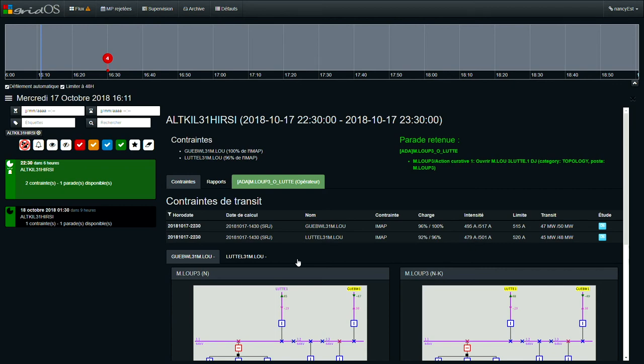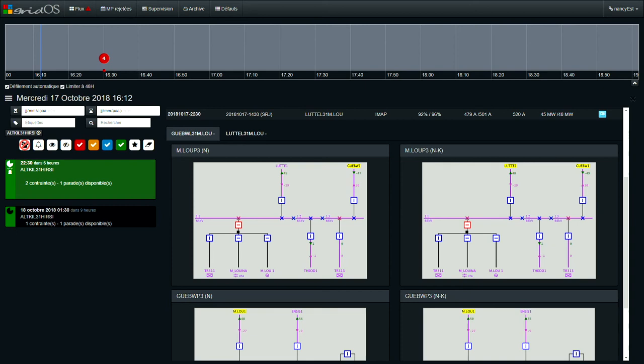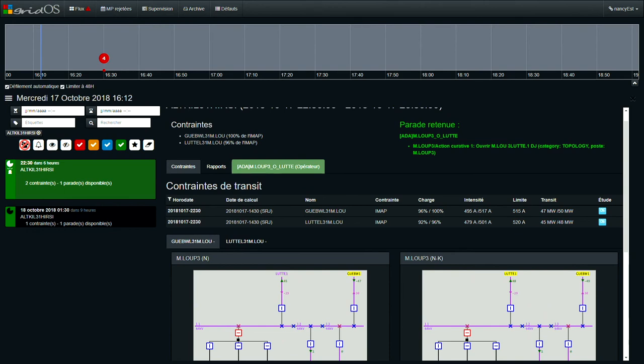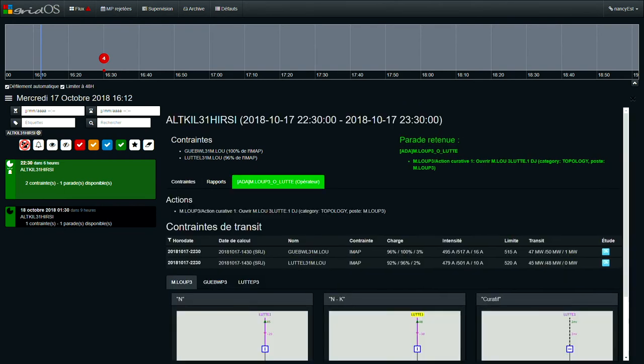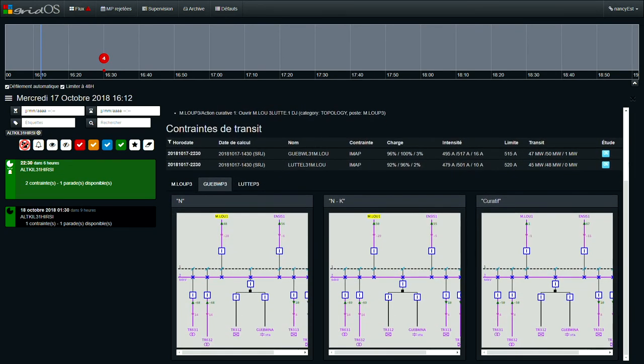So now let me show you a live implementation of OperatorFabric that is being experimented in a control room in France. So here you can see that's the security analysis module. And we can see that we received one notification telling us that in 6 hours there will be an N-1 constraint. And you can see that you have the N situation and the N-1 situation.